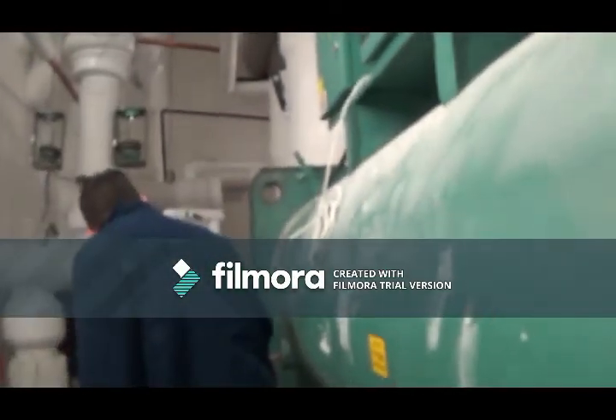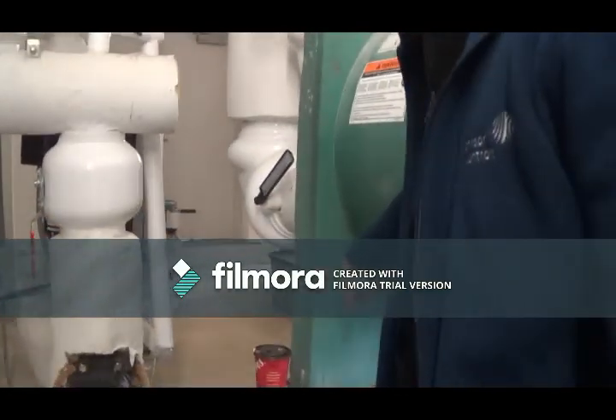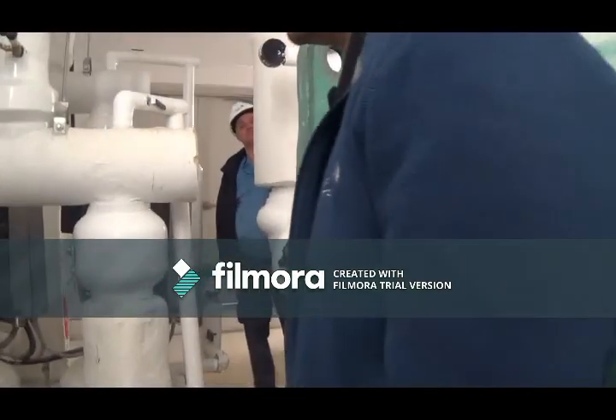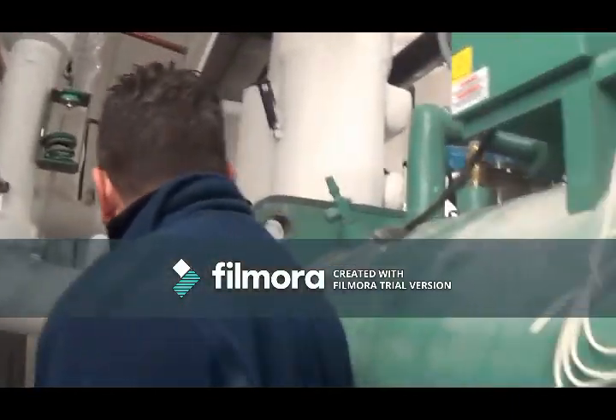Our sight glass here, you might see a level going on the sight glass. Okay. It's going to be a clear fluid, and there might be a little bit of foam on the top. Not just going to be your oil on the top there. That's going to be on that side of it.